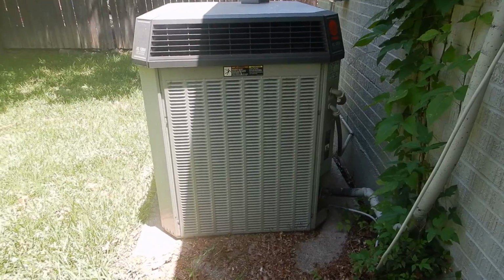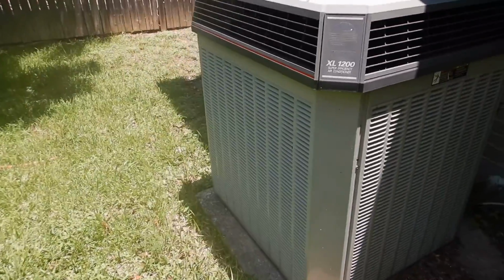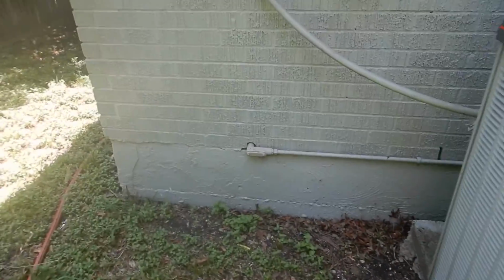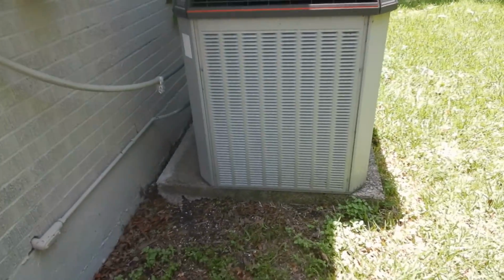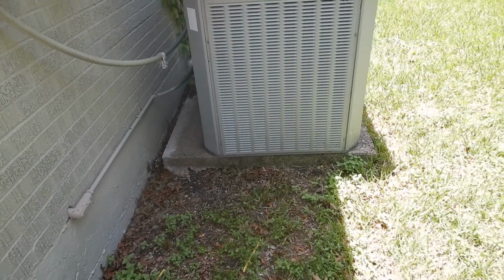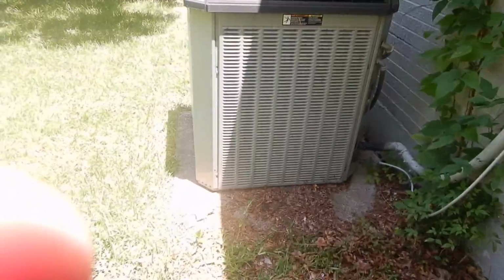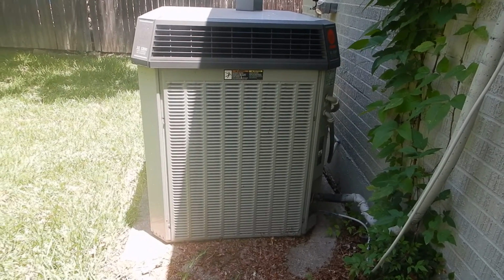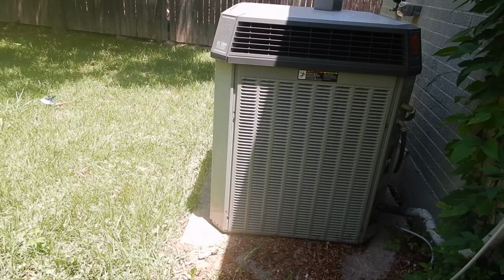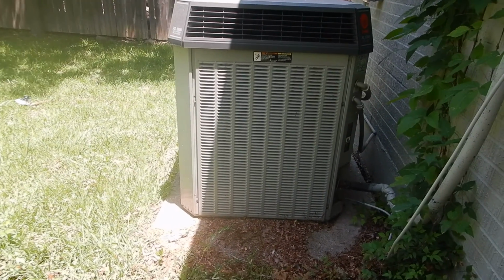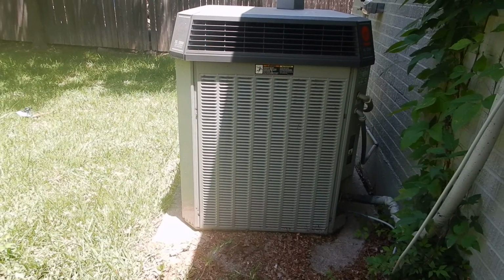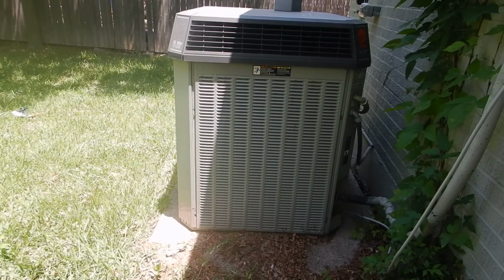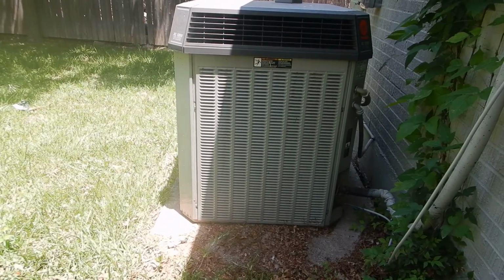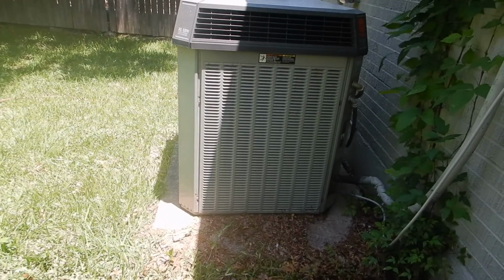It relies on a refrigerant called R22. The brand name is Freon. Freon is not illegal. I cannot condemn a condensing unit based on its age or the fact that it uses R22 instead of a different refrigerant such as R410A. R22 is no longer manufactured in the United States, and it's no longer imported legally. Do they have stockpiles of it? Yes, they do. Is it expensive? Yes, it's expensive. They also have drop-ins available that are not as efficient as this inefficient system, and they're expensive as well.